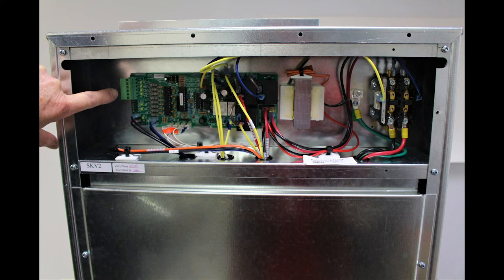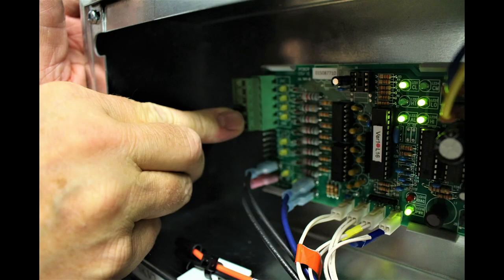Here's the circuit board. I'm pointing at the Molex connector where the thermostat is connected to. The LED lights show a cooling call, low and high fan operation, and that there is no alarm.